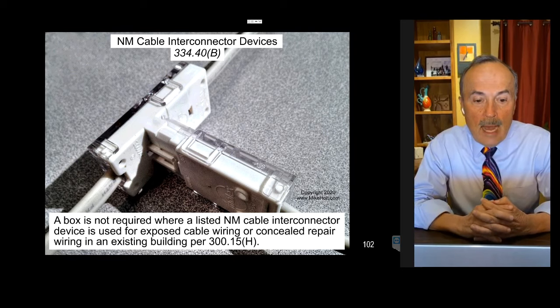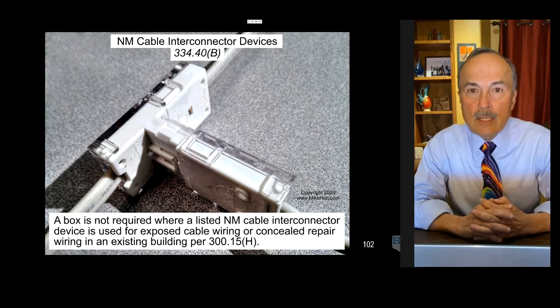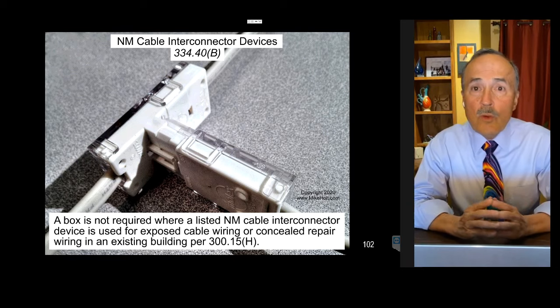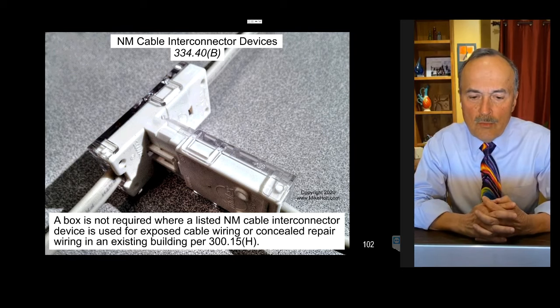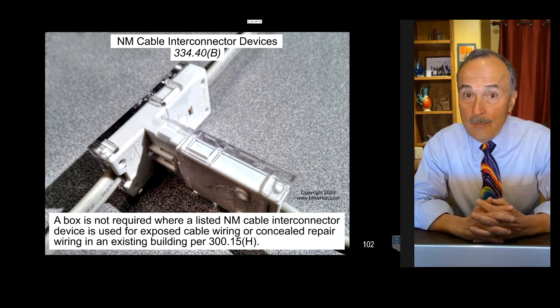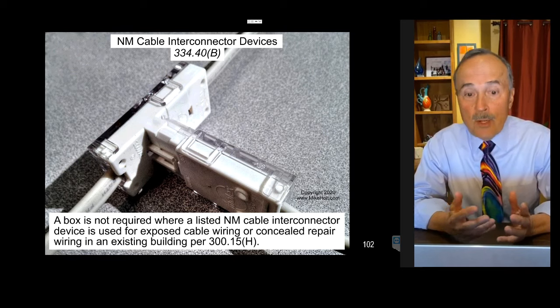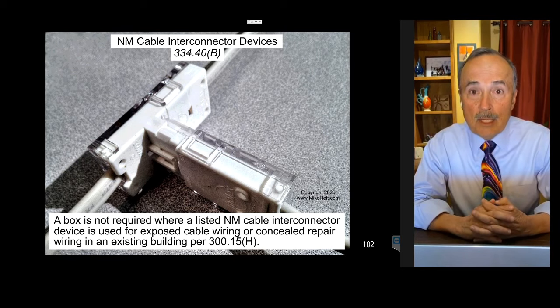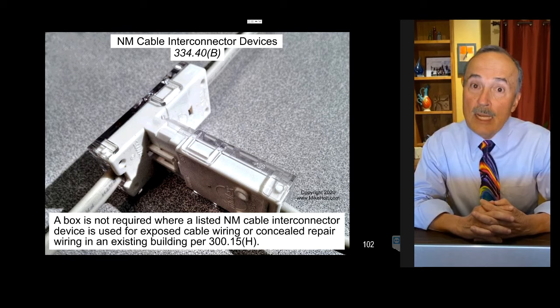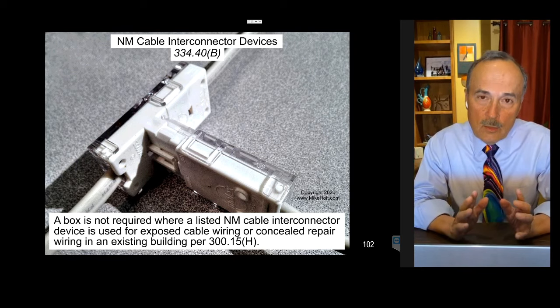334.40(B) is in NM cable. It says a box is not required, or a listed NM interconnector device. So it's called an interconnector device. That's the UL listing title of that. We call it a splice kit. A box is not required where a listed NM cable interconnector device is used for exposed cable wiring or concealed repair wiring in an existing building per 300.15(H). Whether it's exposed or concealed, it doesn't really matter.